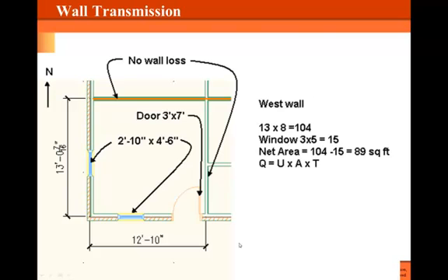If you look at this example here, I have a room which has a wall of 13 foot and 12 foot. Over to the right, I'm discussing the loss through the west wall. This room has a loss through the west wall and it has a loss through the south wall. So we would have two sources of loss through the walls. And then we would have a loss through the floor and a loss through the ceiling potentially. The wall that you see here and here, these two walls do not have any loss because they are conditioned space on the other side of that wall.